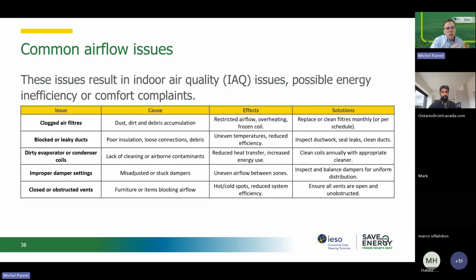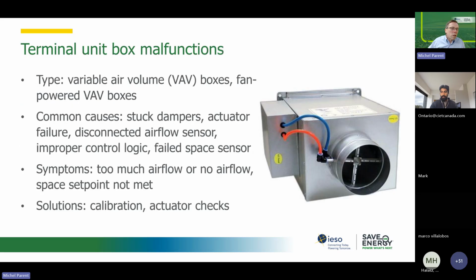Whereas for a constant flow system, dirty filters will create all kinds of issues with air quality. You may not be able to get enough cooling, but in terms of fan power, it will actually use less power with clogged filters, which is kind of odd, but it's always something that is good to know. You don't leave clogged filters, don't get me wrong, but you need to know what the consequences are when you change that: it is to improve air quality, improve cooling capacity and heating capacity, but not to save fan power.